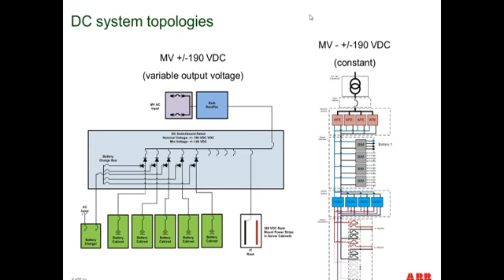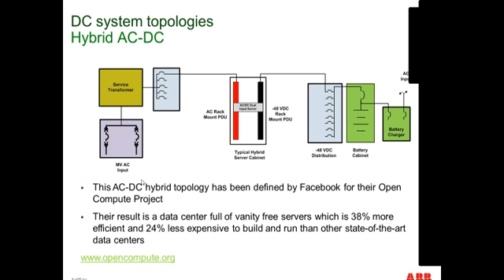One last topology, which John spoke about earlier, is a hybrid AC-DC system used by many participants in OpenCompute.org, championed by Facebook. This topology uses straight AC directly into a rack-mounted PDU, so there's no UPS on the AC side. For backup, leveraging dual input PSUs on the servers, we use either a 48 or 380 volt battery system that provides uninterrupted power during an outage. Batteries are generally sized for short run times, just enough to start your generator, though you can extend the run time if you choose.